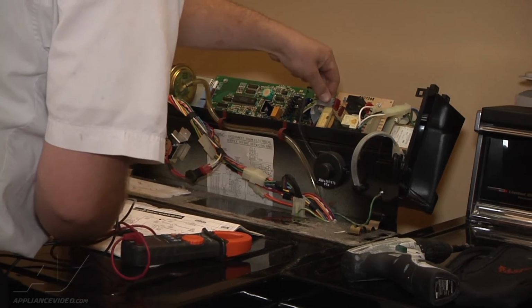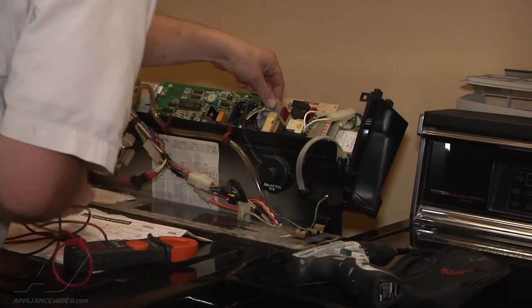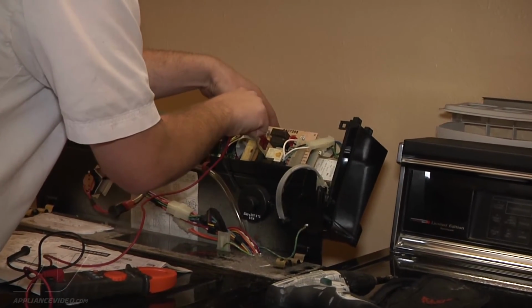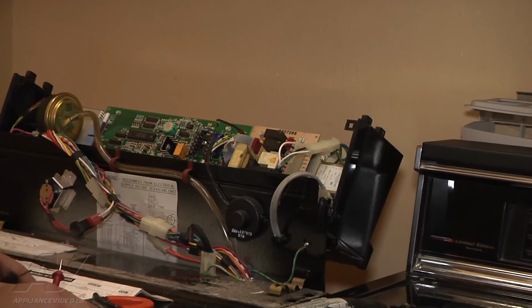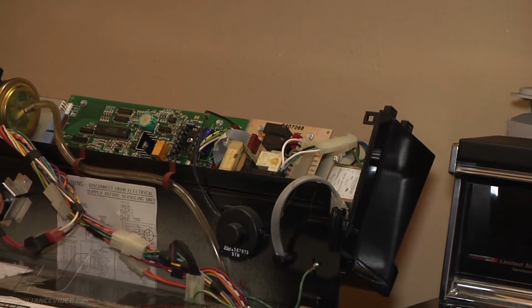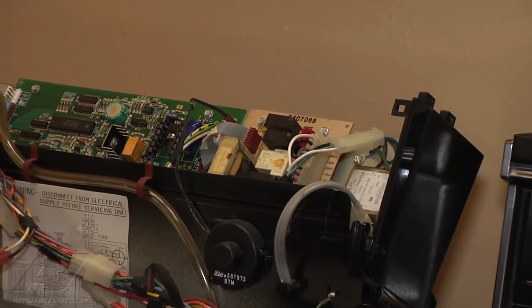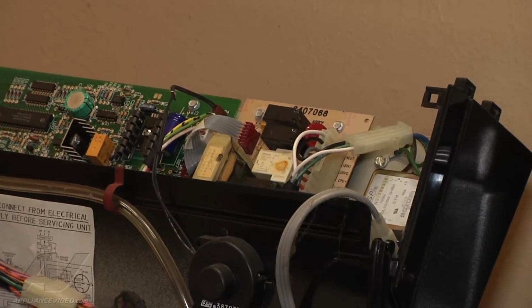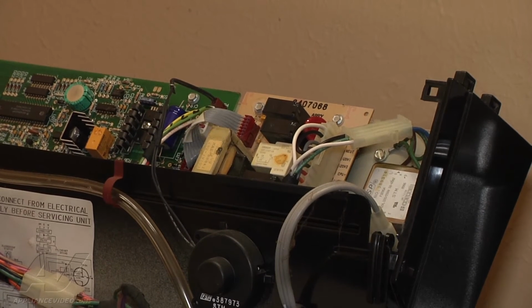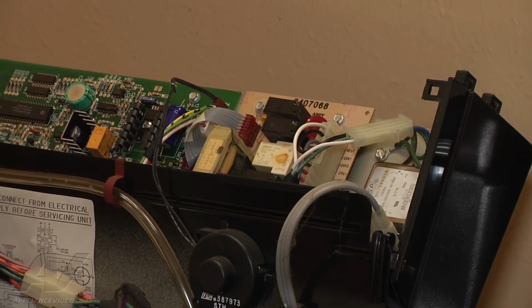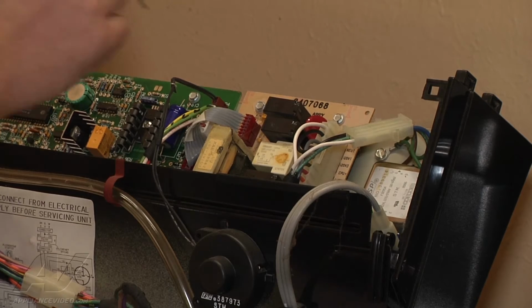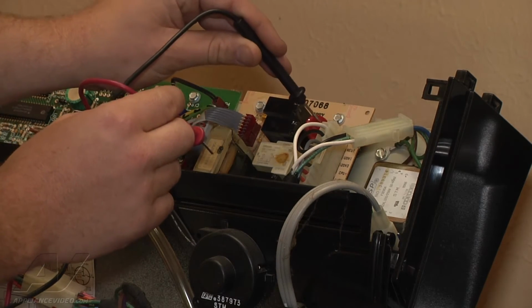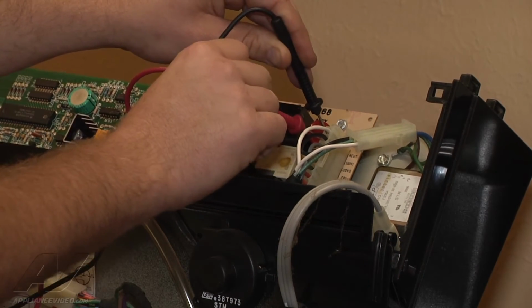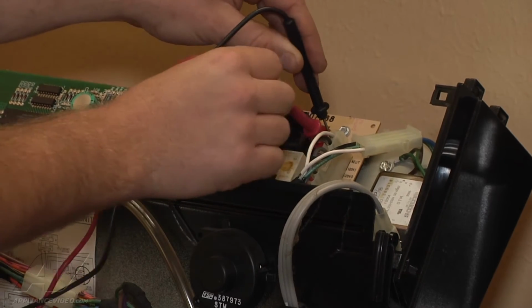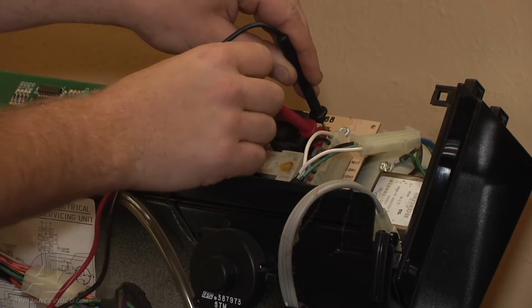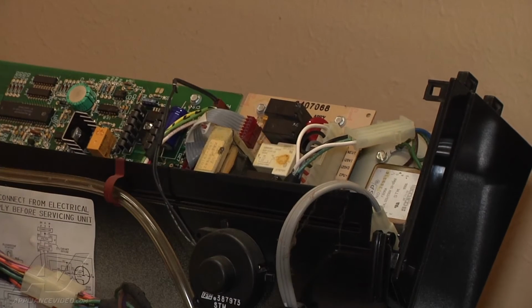We're going to plug back in our RP2 connector here, and what we're going to do then is check for that 120 volts AC. So we're going to set our meter to voltage, and that was pin 1 and pin 2 of the RP3. This is our RP3 connection, pin 1 and 2, starting at the top. It's going to be our black and white wires, and we do have 120 volts there.